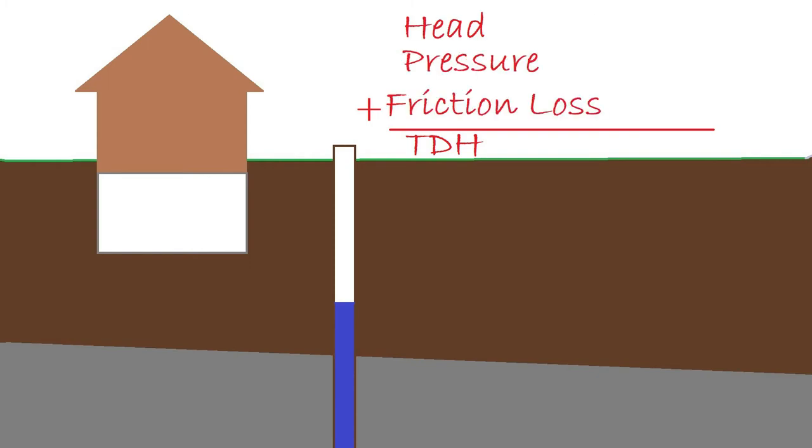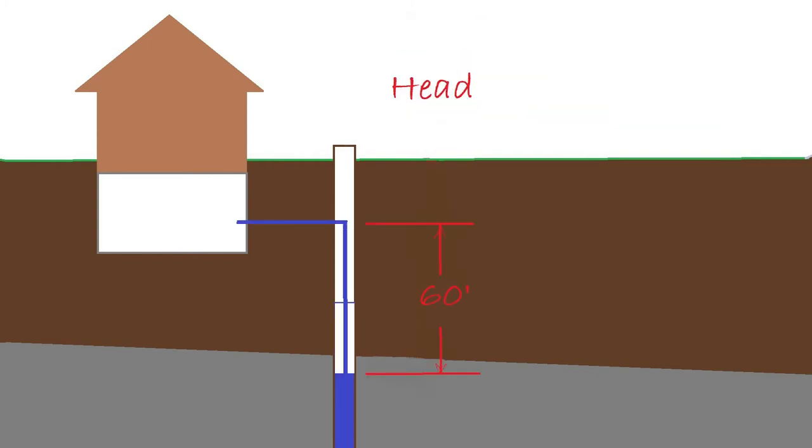To determine what pump to use, we're going to have to figure out our TDH, which is total dynamic head. Total dynamic head is the sum of three values: head, pressure, and friction loss. Head is simply the vertical distance between the pumping level and the highest point of the water system. For simplicity's sake we'll just say that it's the well tank in the basement, and it's measured in feet of head. In our case it's 60.